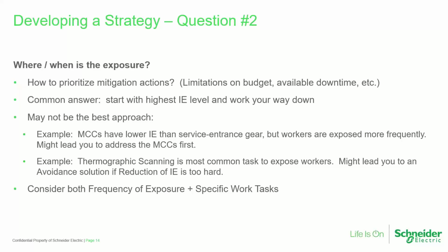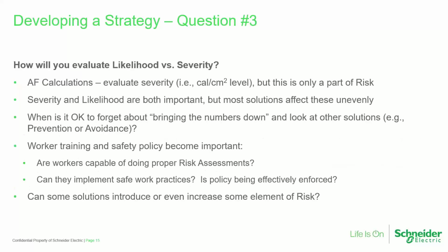Another example, I said, when is the exposure? In some facilities, doing the infrared scans may be the most common task that would expose workers to hazards. Well, there's a case where it might lead you to one of those avoidance solutions that we talked about if reduction of incident energy was too hard. Maybe instead of having to replace circuit breakers to get something that can operate more quickly, or adding relays or whatever, maybe you just put in those infrared windows or those thermal sensors. You eliminate the exposure on the task that is really causing you the biggest problem, and move on that way. So considering both the frequency of exposure and the specific work task can help you sort out the solutions as well.